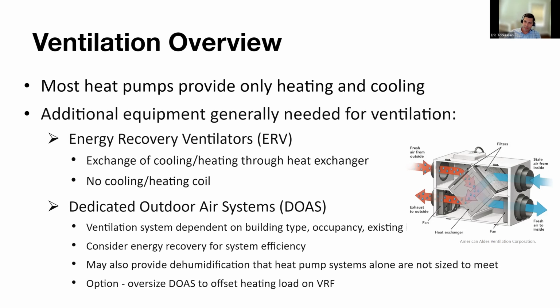These air streams pass through a heat exchanger that transfers both moisture and heat from your exhaust air to your incoming air. So really efficient. All that you're using is fans. And it's really so you're not just, you spent all this energy to get that 95-degree air in the space down to 72 degrees. Instead of just sending that right off to the atmosphere, you can now do a heat exchange so that 95-degree air coming into your space, once it goes through an ERV, might have a temperature of 82 degrees. So those are ERVs.